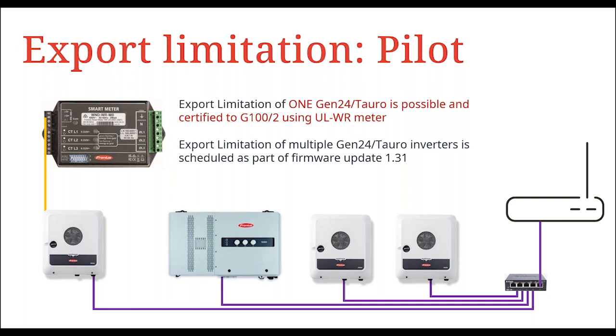First of all, we have the export limitation improvements. At present, we can install a Fronius smart meter and connect that to one inverter, one Primo Gen24, one Simo Gen24, or a Tauro inverter. All the other devices are currently not communicating with that, so all the export limitation has to be through that one device. With the new firmware, we will be able to send a control signal over the local area network using Modbus, and that will then communicate out to all the other inverters on site.